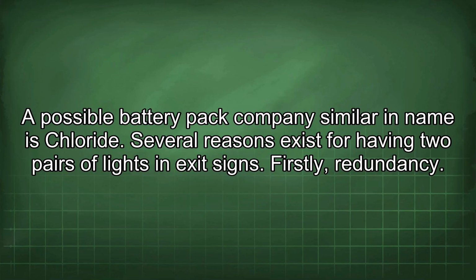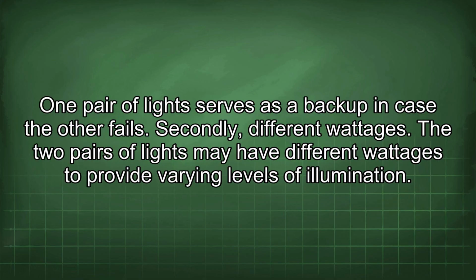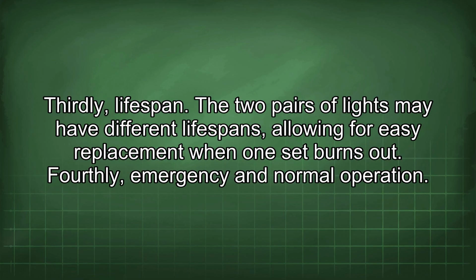A possible battery pack company similar in name is Chloride. Several reasons exist for having two pairs of lights in exit signs. Firstly, redundancy. One pair of lights serves as a backup in case the other fails. Secondly, different wattages. The two pairs of lights may have different wattages to provide varying levels of illumination. Thirdly, lifespan. The two pairs of lights may have different lifespans, allowing for easy replacement when one set burns out.